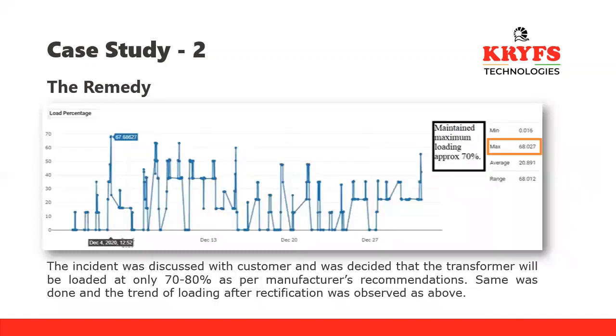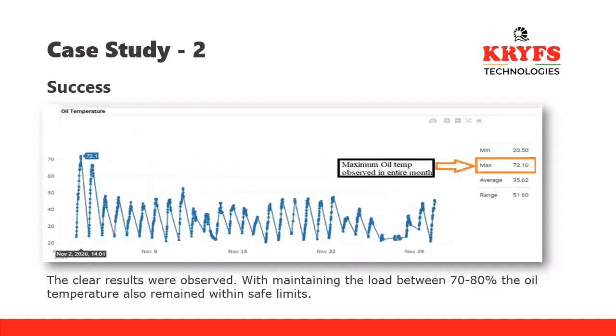Being a transformer company, we suggested they keep the transformer on a normal load of around 70 to 80%, and thanks to the APCPDCL, they maintained the transformer from the next month at a maximum of 68%. You can see from the graphical representation of our BOLA dashboard that they maintained the transformer at a maximum of 68%. Because of this, the oil temperature stayed within limits, since they maintained the load percent of the transformer.